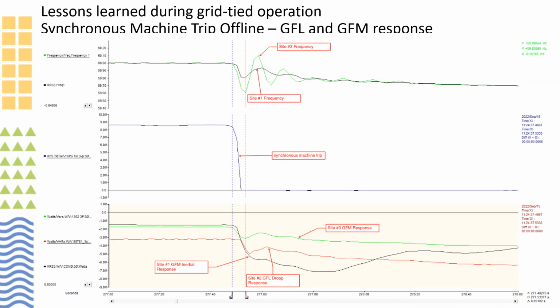We did things pretty simple. We operate our PV battery systems mostly in just a fast frequency droop response, volt var frequency watt. And then that's basically at the inverter terminals. Above that, we still will send dispatch signals.